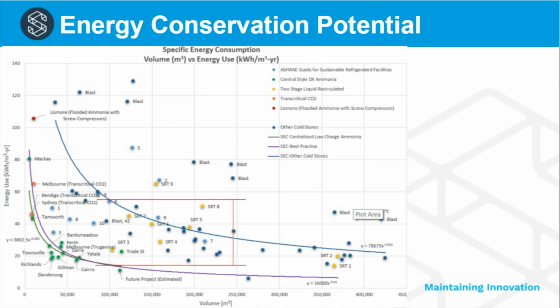So in terms of energy conservation potential, and this is taking a, shall we say, a big macro look at the global refrigerated warehouse industry, if we take a 100,000 cubic meter cold store and we take the difference between average practice and best practice, we see a difference of a factor of 4. And this is representative of the energy conservation potential that we have in the refrigerated warehouse industry as a broad average globally today. In Australia, for example, more than 90% of existing refrigerated warehouses, and we have more than 100,000 refrigerated warehouses in Australia, do not meet best practice. We know this.